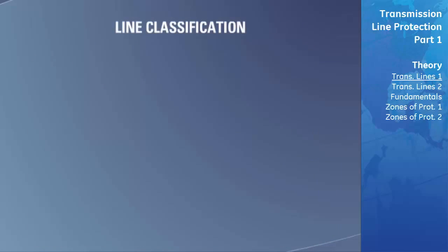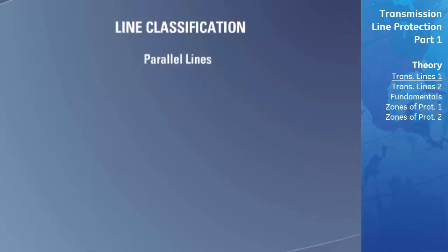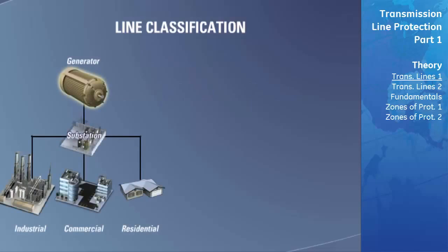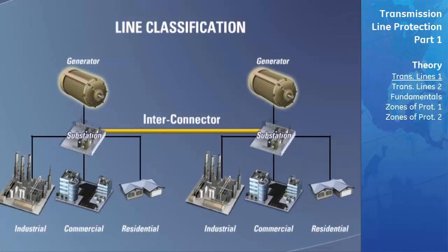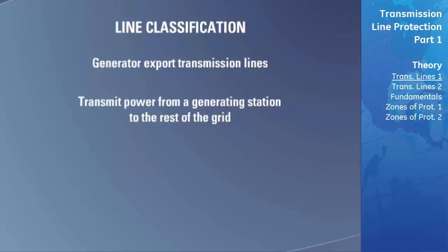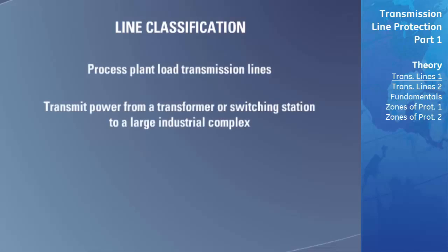Transmission lines can be broken down into one of four main classifications that describe their configuration, the function they perform, and their location in the system. Parallel lines describe a configuration where multiple transmission lines run side by side, done to transmit large amounts of power and provide a redundant path in case one line is shut down due to a fault. Interconnector transmission lines connect one section of a power system to another. Generator export lines transmit power from a generating station to the rest of the grid. Process plant load lines transmit power from transformers or switching stations to large industrial complexes.